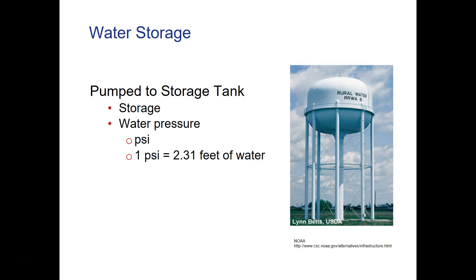When we get into water storage, you pump water from the ground or underground up into a storage tank. These storage tanks are often at the top of a hill or high in the air for a reason: for every foot of height, there is associated pressure. Specifically, 1 PSI equals 2.31 feet of water. So if you pump water up 60 or 70 feet in the air, that really starts adding up into significant pressure just from the water pushing down on top of itself.